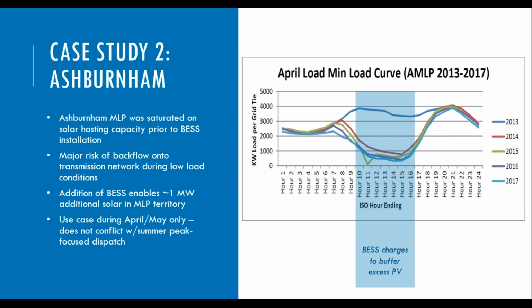The interesting wires type application of this particular storage facility is that the MLP was saturated on solar hosting capacity prior to the installation. You can see their development of a classic duck curve between 2013 and 2014, which had to do with both customer-owned storage within the MLP territory, customer-owned solar, as well as development of a landfill-covering, relatively large PV facility. So the MLP was concerned about a major risk of backflow onto the transmission network during low load conditions.